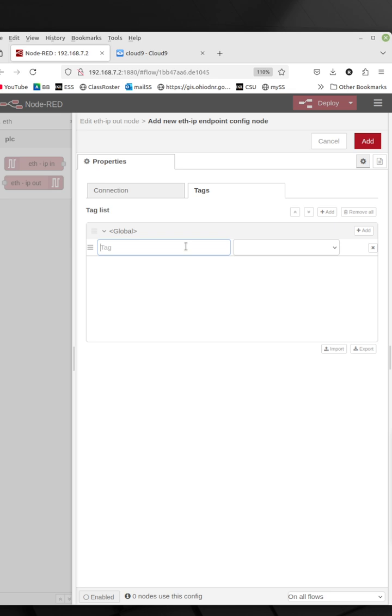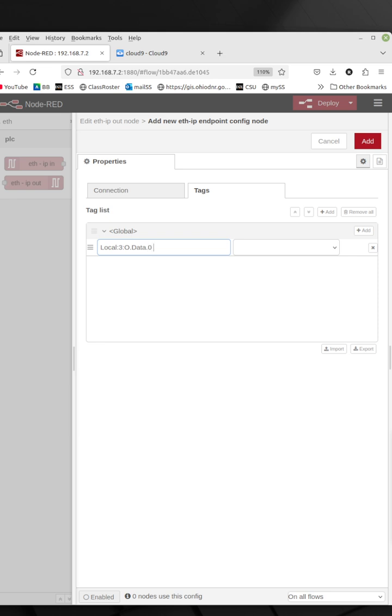Colon, it's module three is my relay module, colon O for output. This is not a zero, this is O for output. So it's module three, which is an output module. And my first relay is bit zero, so I put data dot zero. Now, this spelling, the capitalization and everything needs to be correct.